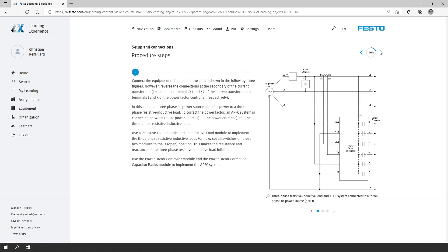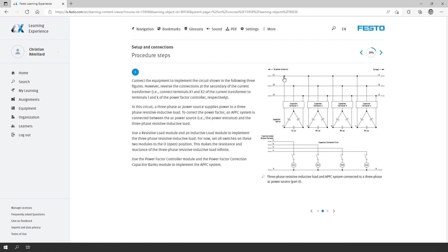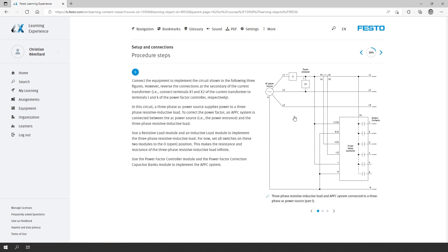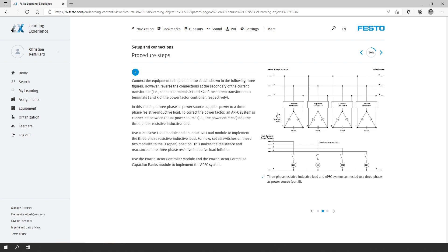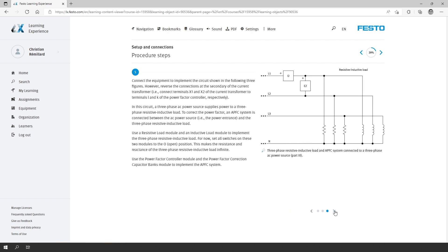Of course, with all the required accompanying schematics. Here is the schematic of the system that we want the student to wire. We can see that from our three-phase power source, we will connect our power factor controller. The capacitor banks will be connected on the next page, as we can see, along with the contactors that allow us to trigger on or off each of these capacitor banks. On the far right, we will be connecting to a resistive and inductive load so that we can change the value of this load and see how the automatic power factor correction is applied.